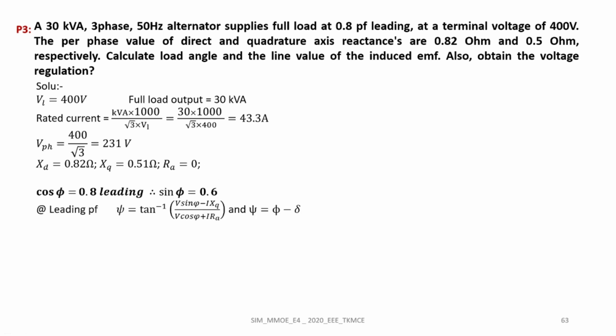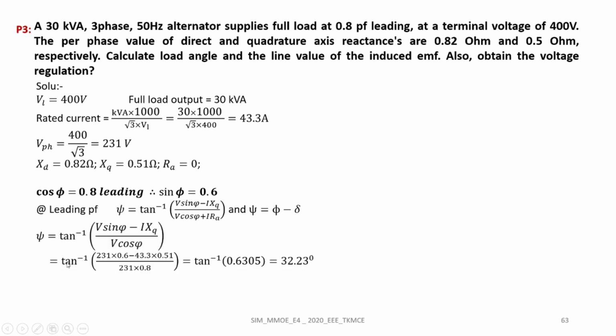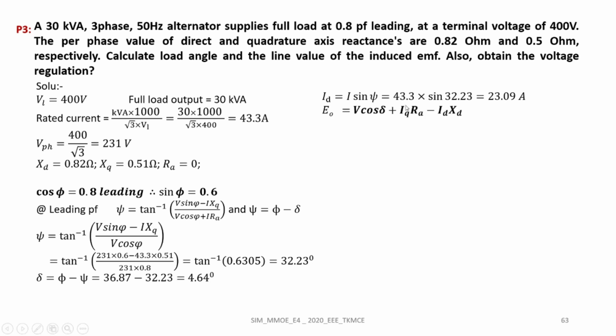Corresponding to the leading power factor case, this is the expression for psi: tan inverse of (V sin phi minus I XQ) divided by (V cos phi plus I into RA), and the angular relation is psi is equal to phi minus delta. Substituting different parameters in this equation, we can obtain psi as 32.23 degree and delta is obtained from this relation as 4.64 degree. Now ID is equal to I sin psi, which is coming as 23.09 ampere, and there is no need of calculating IQ as IQ RA is coming 0 as RA is equal to 0.